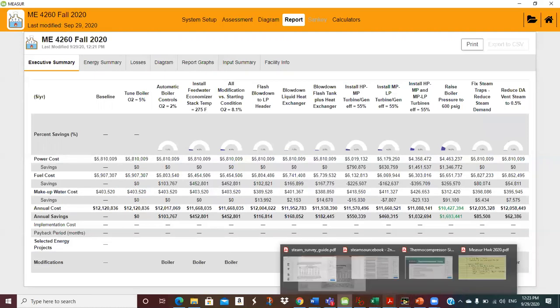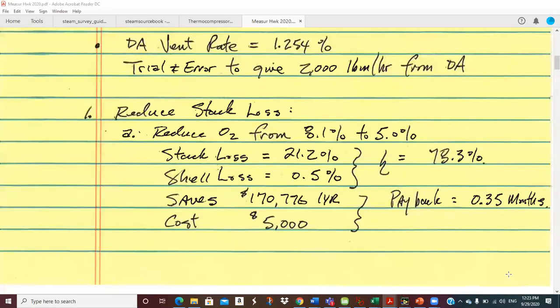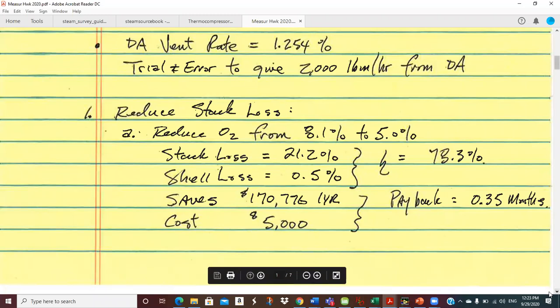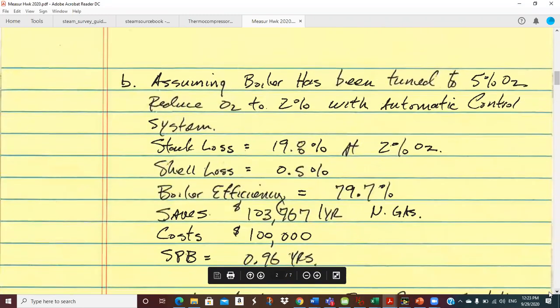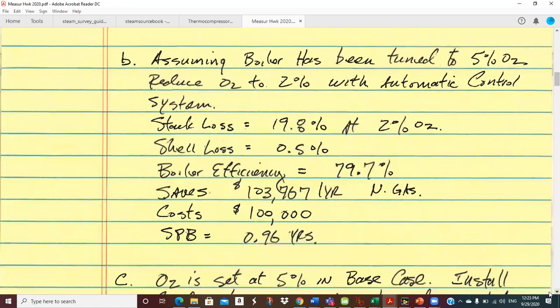So the second scenario now is 103,767 in savings. This one is now zero because I made the 5% my base case — it's running 5% versus 5% so it's not going to show anything. This run is good for looking at this column. This one is a little more costly — probably roughly $100,000 to replace the boiler control system, depending on which one you buy and what the bid comes in. It could be 80, 85, or 125 thousand. At this level we're just trying to put in a good representative number. That gives me about a one-year payback. That's a pretty good investment.